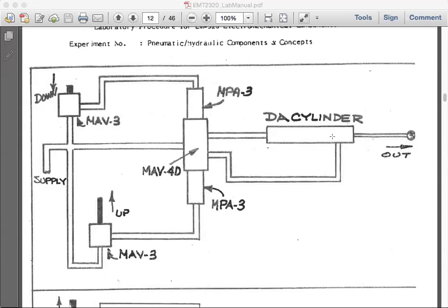So if you fill up the right chamber, it would create a piston to return, and as the piston returns, the pressure from the left chamber would vent through the venting hole because the stem is still down. So any pressure coming from here would vent through this venting hole.